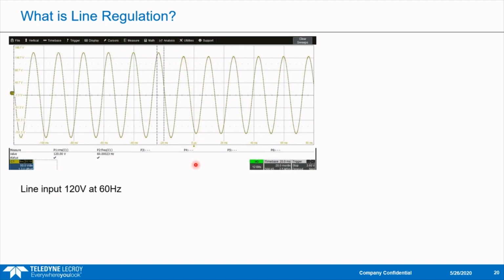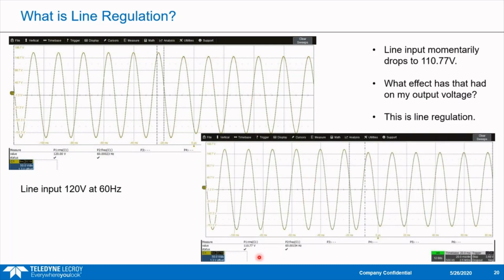When I move the measurement gate over to this end, you can see my voltage at the second half has dropped to about 110.77 volts, still at 60 hertz of course. So I've dropped from 120 volts input to my power supply down to 110 volts input. What effect does that have? This is what line regulation is - the line drops from its nominal value momentarily to a lower value, and we look at what effect that has on the output. That's what the specification is talking about: the change in the output relative to the change in the input. As you can see from those specifications, that's very low.